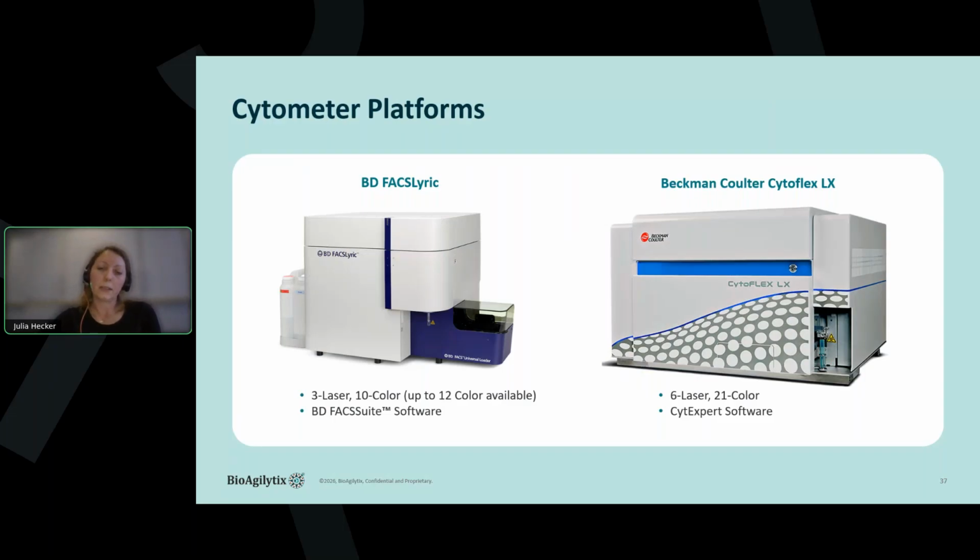The CytoFLEX is a little bit more convenient in the development, because the software is easier to plan. It is easier to plan your 96 well plates, but they both can be used in a regulated environment. The software is qualified and compliant to the regulations. The Lyric, on the other hand, was a little bit faster. So when it comes to high throughput assays, and this is different compared to a plate reader, a cytometer takes some time to measure the samples. So with a high throughput, the Lyric also had advantages in our lab.